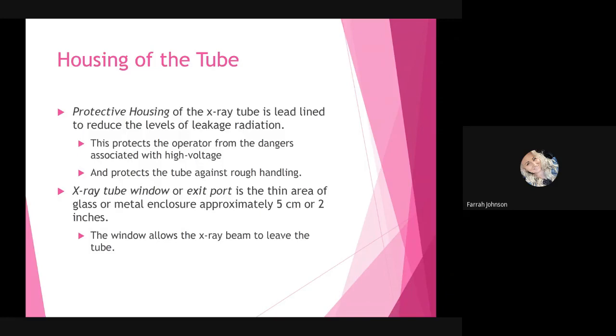Then you have the housing of the tube. So you have your protective housing of the X-ray tube, which is going to be lead lined, and that helps to reduce the levels of leakage radiation. So if there's any photons that are traveling in a foreign direction within the tube, that lead is going to help absorb them before they actually exit the tube. This helps to protect the operator from the dangers associated with high voltage, and it also protects the tube against rough handling.